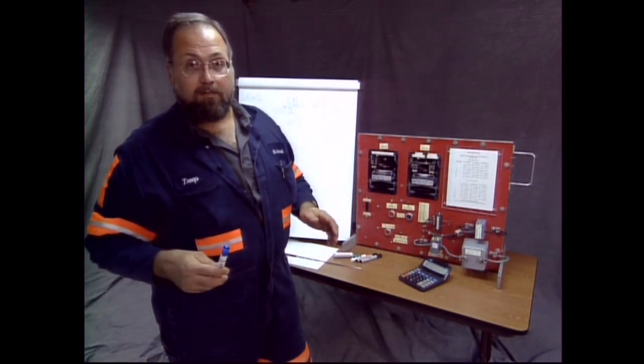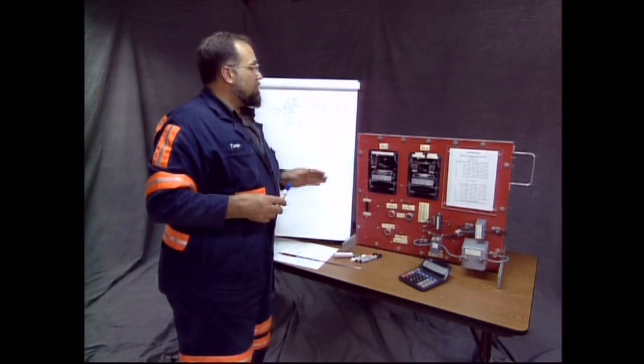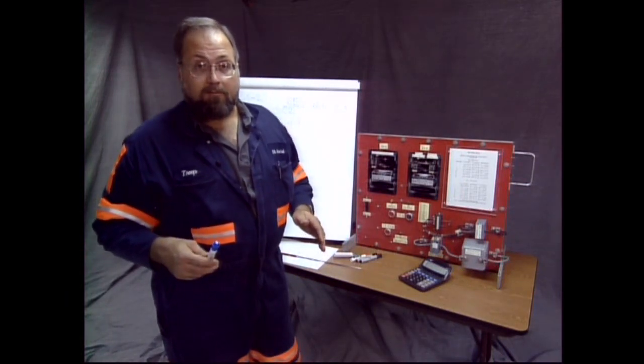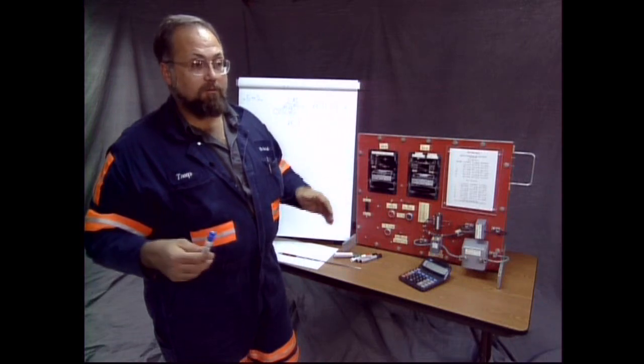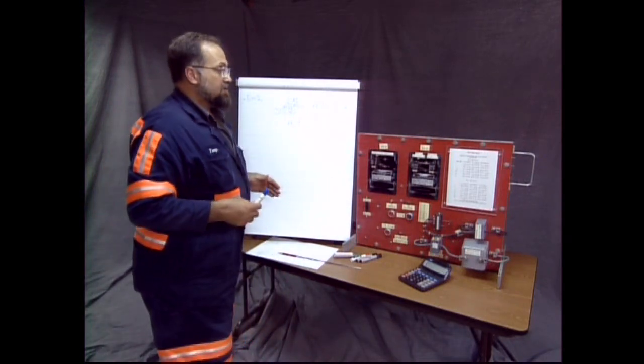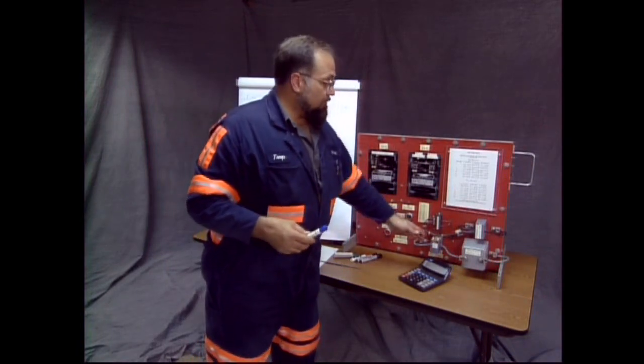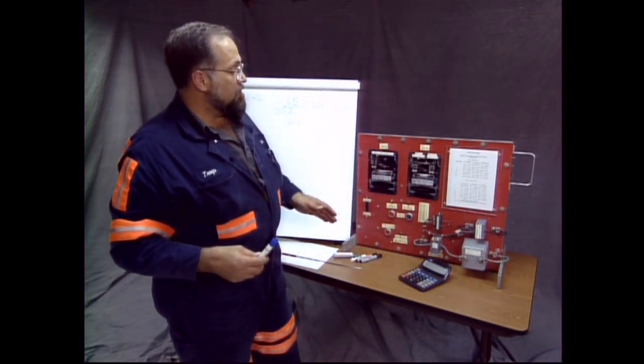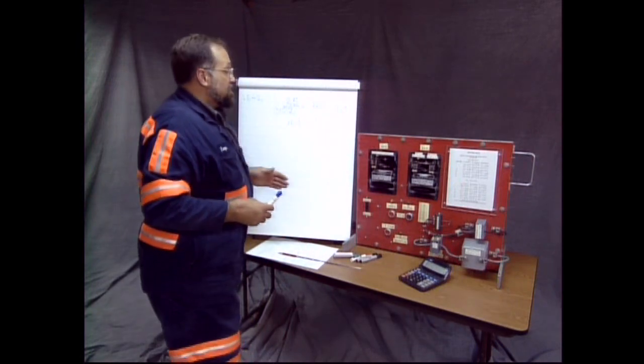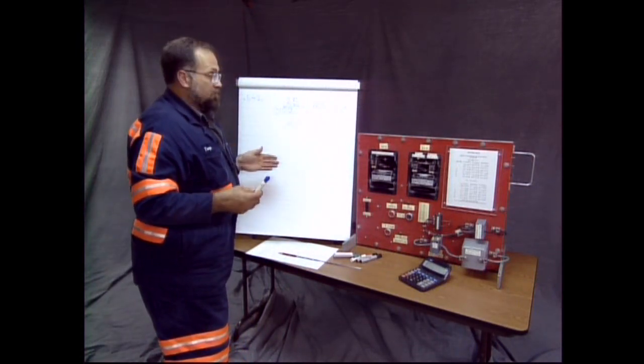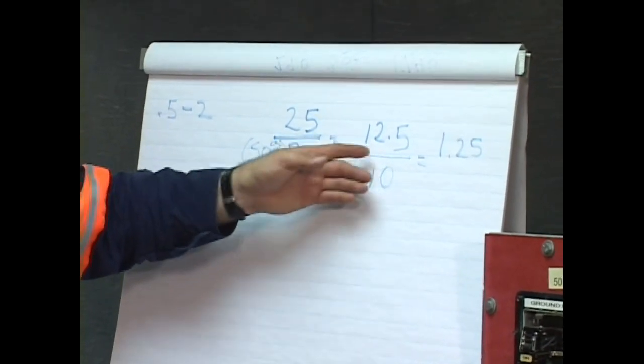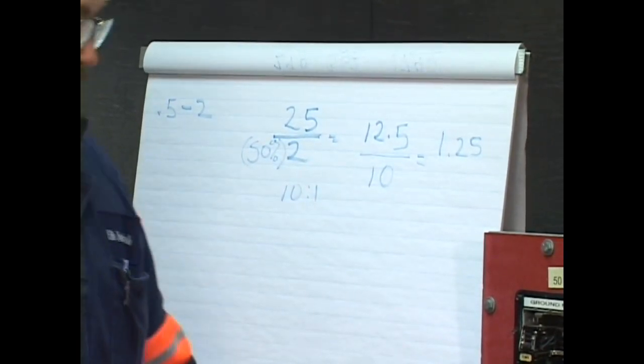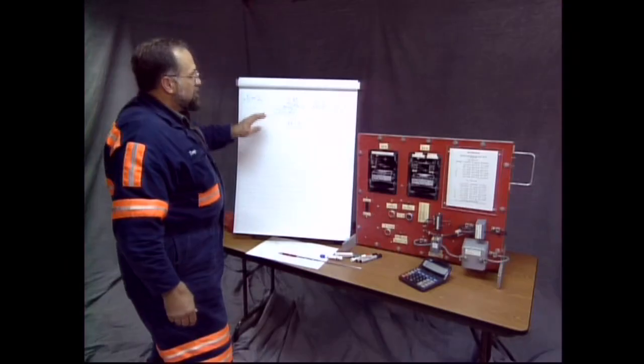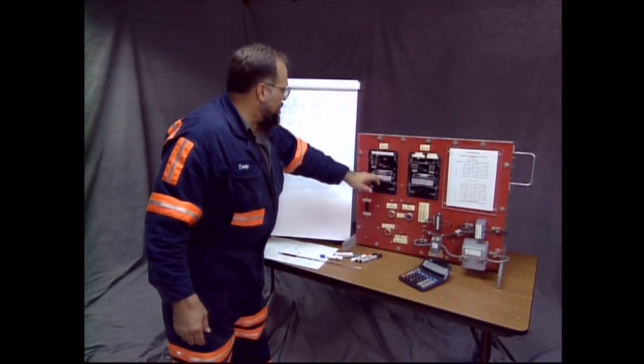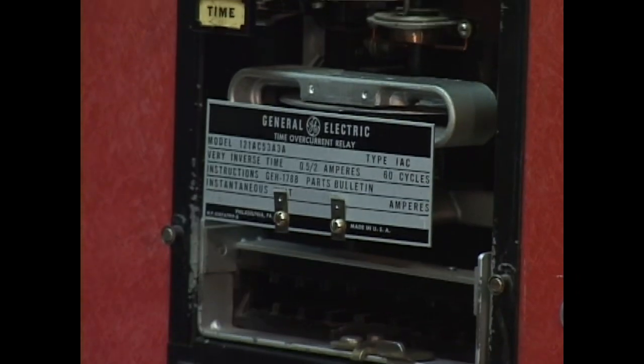Now again, fellas, that's a maximum setting. It's not a recommended setting, the maximum allowed by law. I've never adjusted one as high as that. 5 amps is a good setting for this. Most everywhere you go, 5 amps will be what you find. If you have 5 amps of current flow on the ground conductor, this relay is going to trip most everywhere. But set at a maximum level, you could possibly set it at a tap of 1.25 for a value of 12.5. Now, we spoke of the range of the relay. That's listed here, 0.5 to 2. That's on the nameplate.